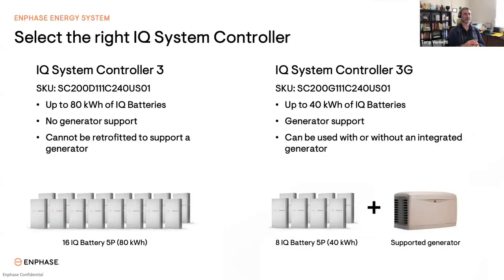So here we have the 2 different systems. The first one, the IQ System Controller 3, is ideal for allowing for maximum energy storage, battery storage on our system. The IQ System Controller 3 can have up to 80 kilowatt hours of capacity, which would be a total of 16 of the IQ Battery 5Ps.